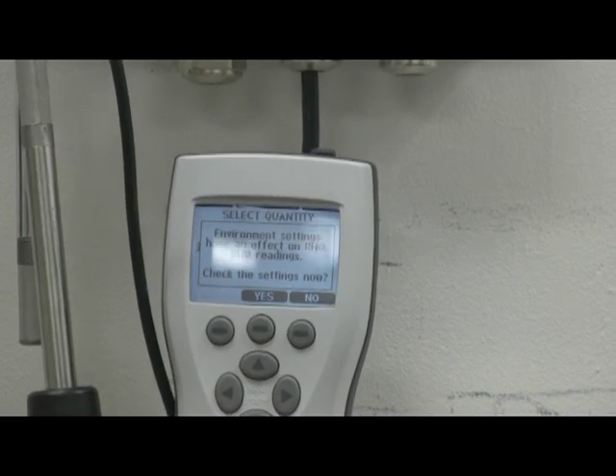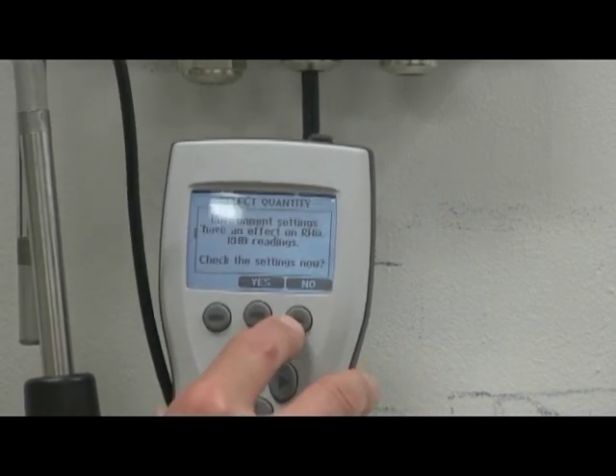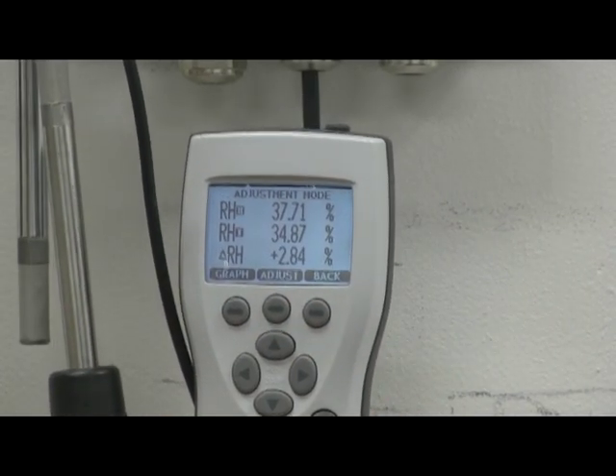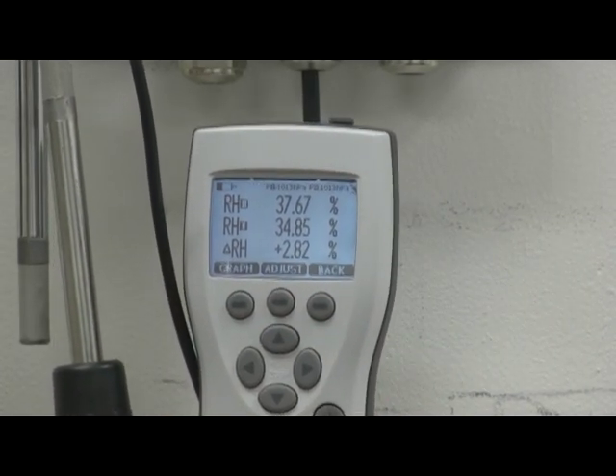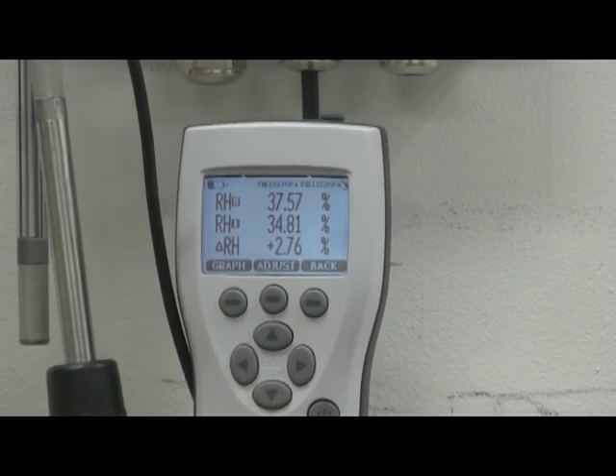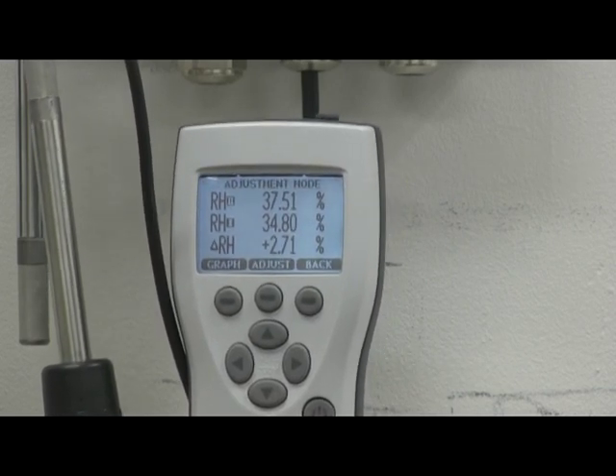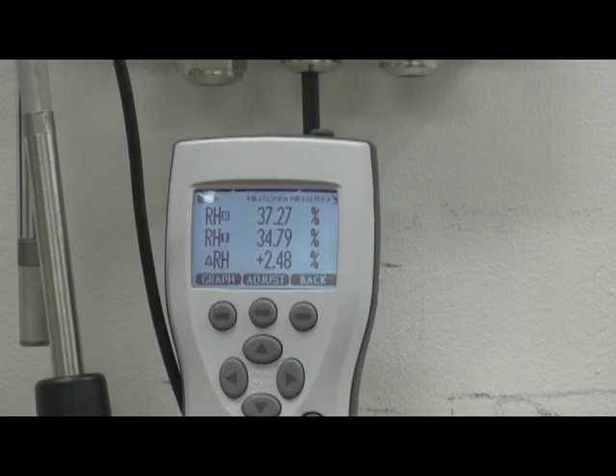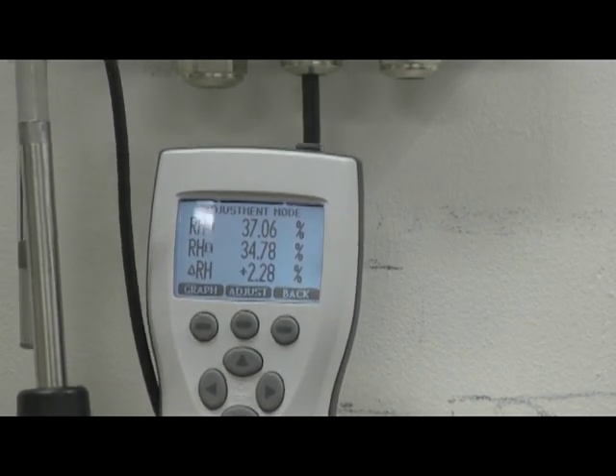You will now see the adjustment mode flashing at the top. At this point, it's best to place the probes side by side, keeping a distance away from them, since your body heat and moisture from your breath will affect the accuracy of the readings and calibration.